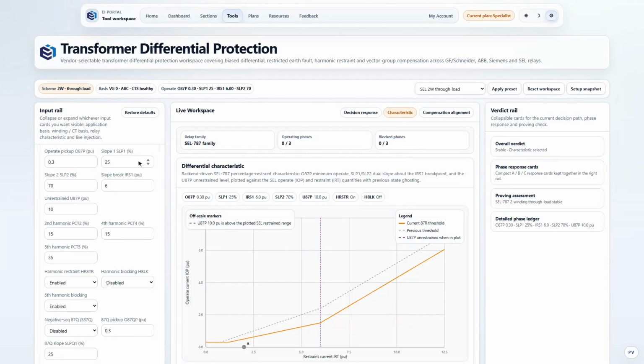Now let's apply an internal fault. Both operate and restraint read 4.382, one-sided infeed straight into the zone. Below the slope break, the threshold is 25% of restraint, 1.096, and the operating point lands miles above the slope, resulting in a biased differential trip.